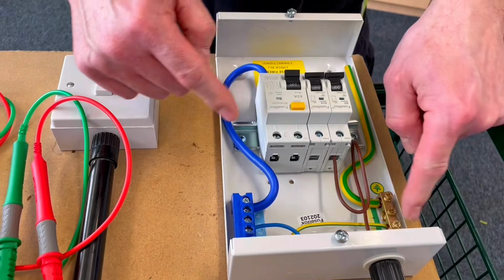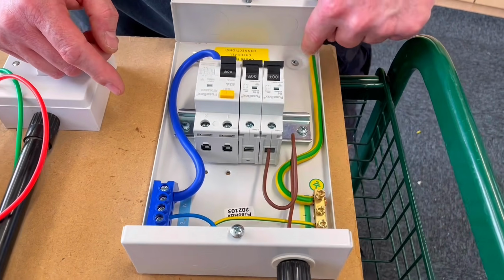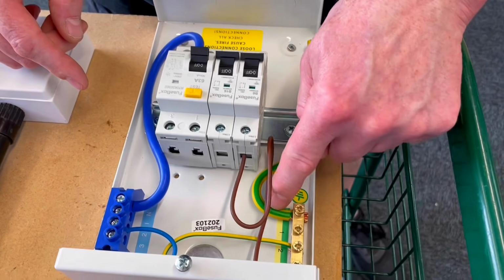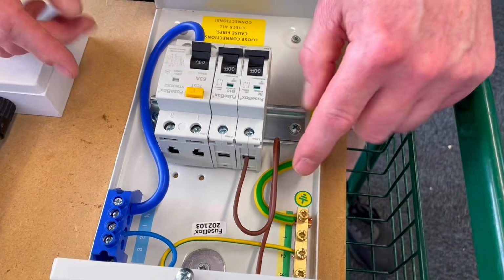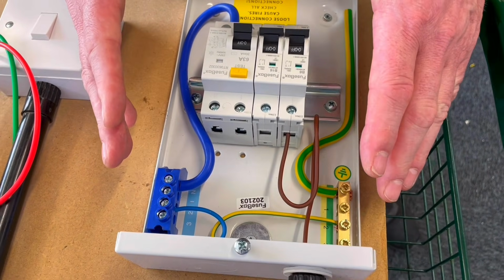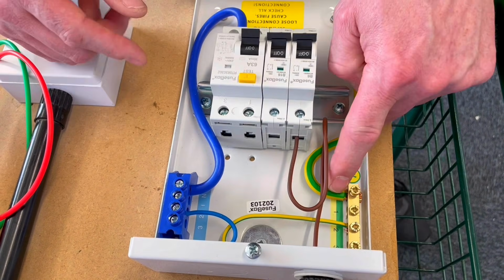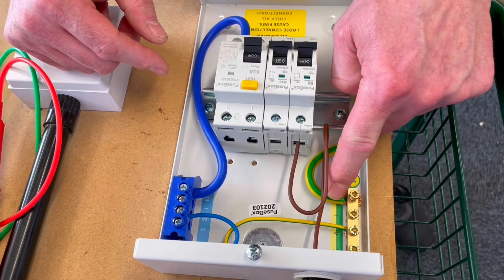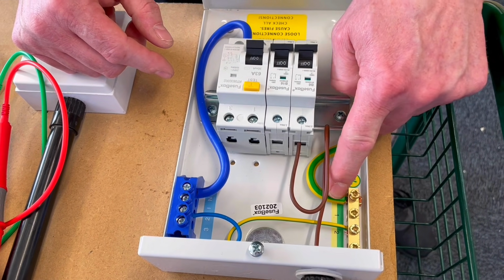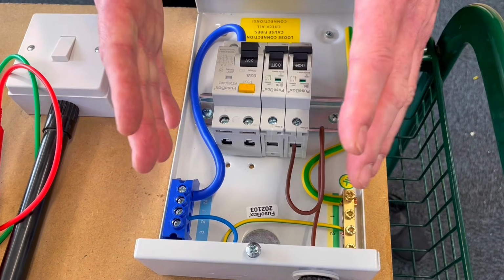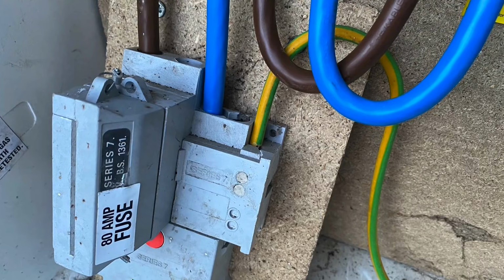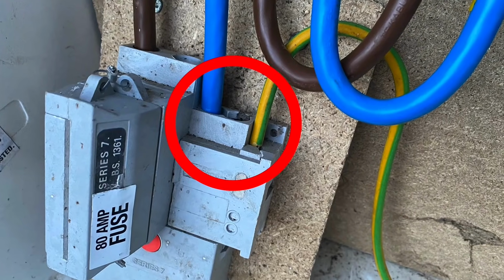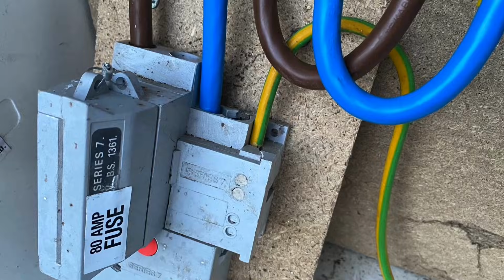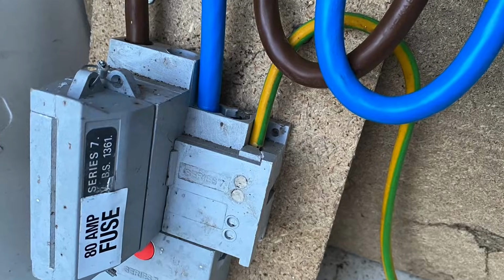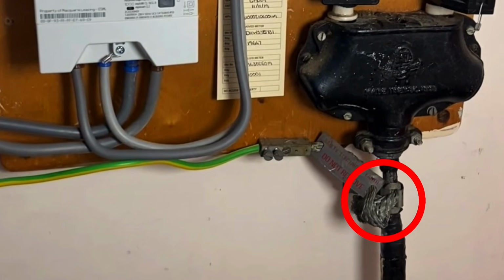So we leave everything in here in the off position. Now, I've left one little conductor here, which you can see doesn't go anywhere, for a reason. This is to remind you that when carrying out the insulation resistance test, the earthing conductor, which comes in with the tails, must be connected to the source earth, as well as any bonding. So in a TN-C-S earthing arrangement, this green and yellow conductor would go off and be connected to the cutout where the neutral is. And in a TN-S system, this goes to the sheath of the cable.